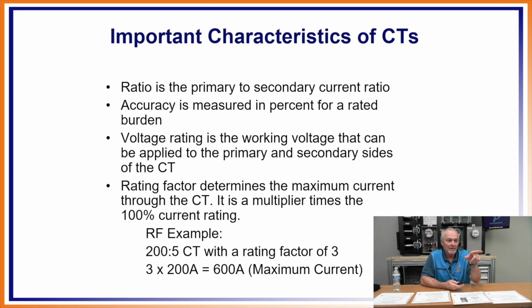So we can see that the burden definitely affects the accuracy, because the nameplate says accuracy at a burden. So it's telling you at that burden what the accuracy is. So if you put too much burden on it, obviously that doesn't hold true anymore, right? Voltage rating is the working voltage that can be applied to the primary and secondary sides of the CT. So as we said earlier, it's the voltage that the CT is operating at. Rating factor. The rating factor determines the maximum current through the CT. It is a multiplier times the 100% current rating.